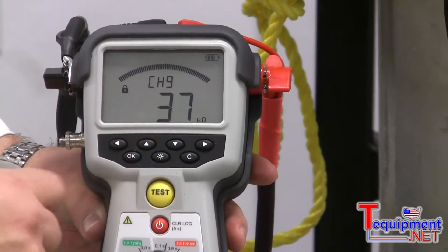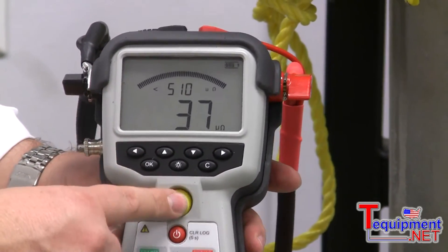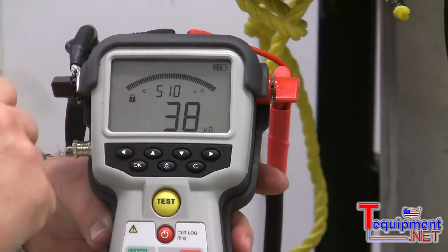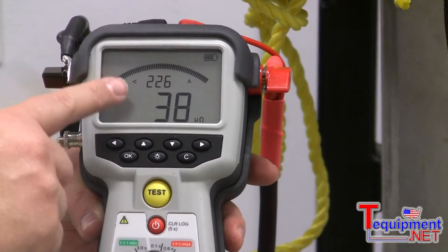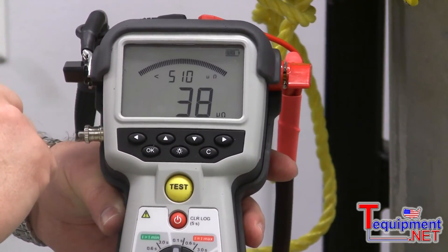You see, I cannot do any tests while the lock is still on. The lock is off now, so I can do another reading. And I've done the reading at 226 amp, and as you can see here, there is also pass-fail at 510 micro ohm.